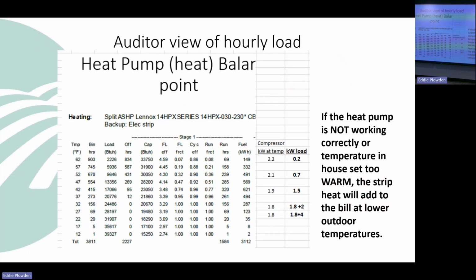And as it gets colder outside, it really adds to what we were talking about earlier, how much is the use per hour on an appliance. In the milder temperatures, before it's really having to run a lot, you're talking about less than 1 kilowatt hour an hour. Down in the low 40s, running all the time just on the compressor, it's like 1.5 to 2 kilowatt hours an hour, similar to a cooling system. But when you drop down below the balance point, then that strip heat comes in. You start adding up, and it's 3, 4, 5, 6 kilowatt hours an hour for the heat when you have that strip heat running. So it's very important to maintain that the unit is working properly. And then your thermostat setting, not having the house really super warm, really adds to a bill.